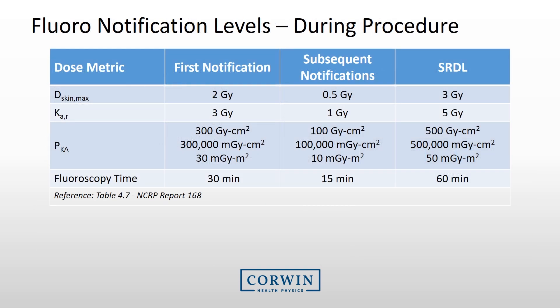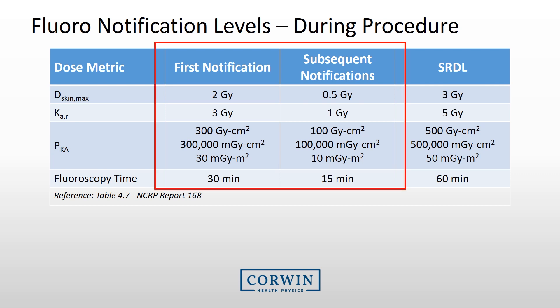It is recommended that notification levels be established to inform fluoro operators during a procedure when a designated level is exceeded. At that point, the operator should determine whether the radiation risks are warranted and if the procedure is to continue. Recommended notification levels include peak skin dose, air kerma at the reference point reported in gray or milligray, and the air kerma or dose area product. Once the first notification occurs, continue notifying the operator at subsequent notification levels.